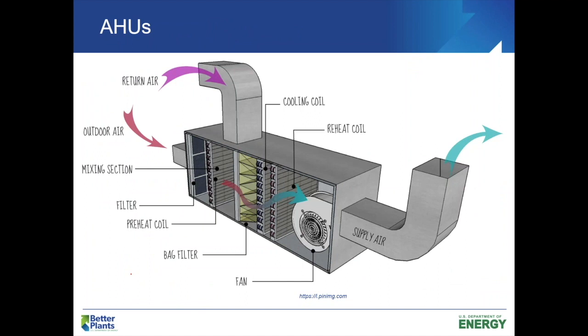One of the most common because it pulls everything together is the air handling unit. Here's a diagram of a really basic air handling unit — you probably have several of them on the roof working right now. What it's doing is taking both return air as well as outdoor air, bringing it in, filtering it, then preheating it, and pushing it through. There's a cooling coil and then a reheat coil before it gets pushed out into our space. The cooling coil is where we might take our chilled water and dump it in, whereas the reheat coil could be steam or hot water.